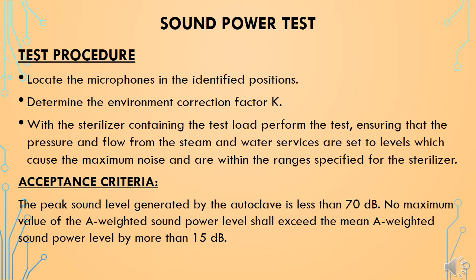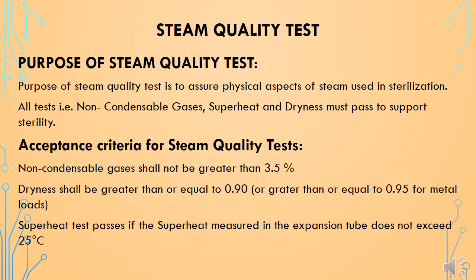The acceptance criteria for the sound power test is that the peak sound level generated by the autoclave should not be more than 70 dB, and no maximum value of the A-weighted sound power level should exceed the mean A-weighted sound power level by more than 15 dB.